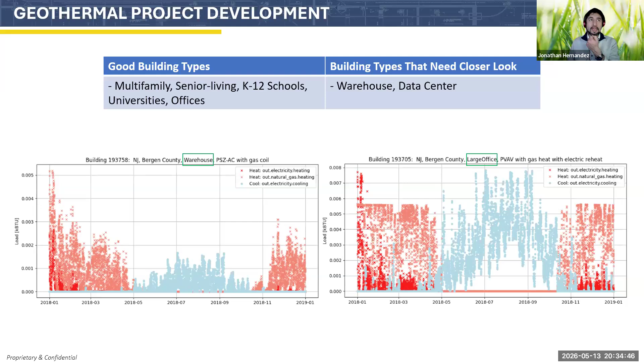You can build on top of these. The only time you couldn't is on a pressurized foundation slab - that's more of a water pressure issue, and it could probably be solved with some drilling technology, but right now that's the one time we try to avoid it. Otherwise, if it's an open field, building on top of the bore field isn't an issue - the pipes come up, bend 90 degrees into trenches usually 3 feet below grade, into the mechanical room, into the buried vault, etc. That's really important for retrofitting health facilities.